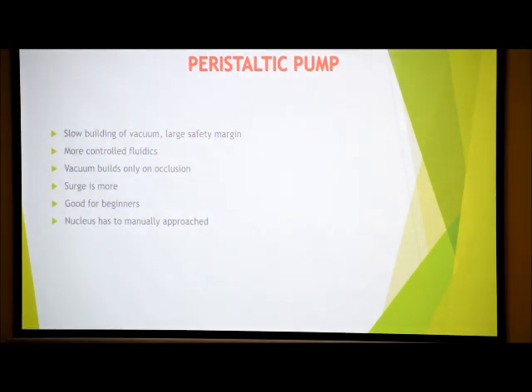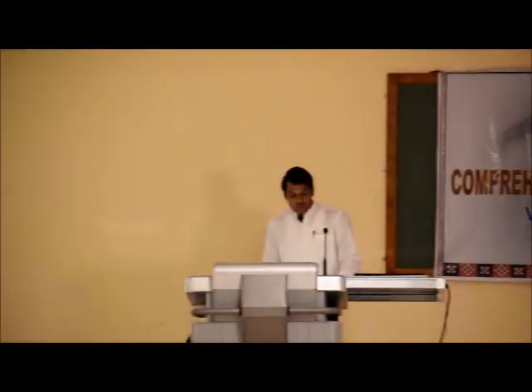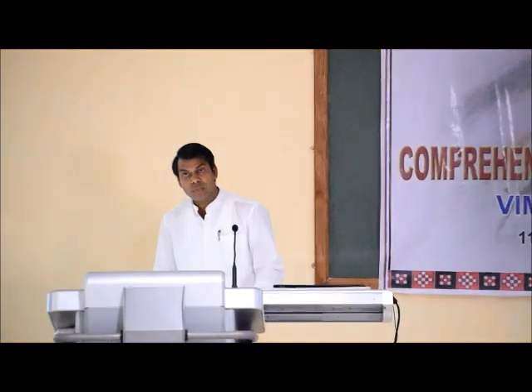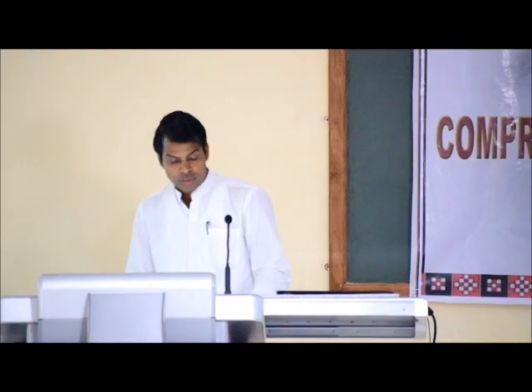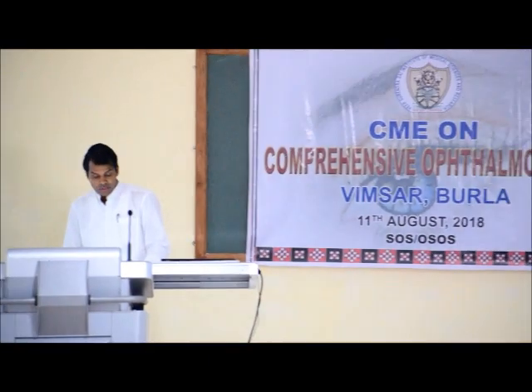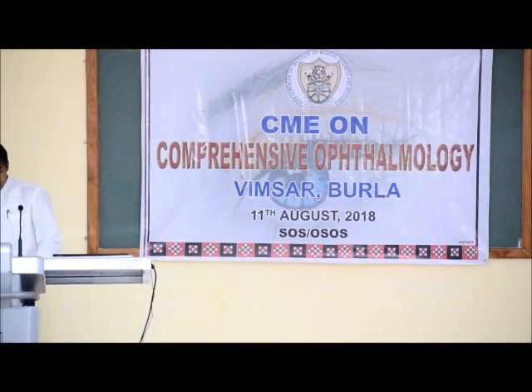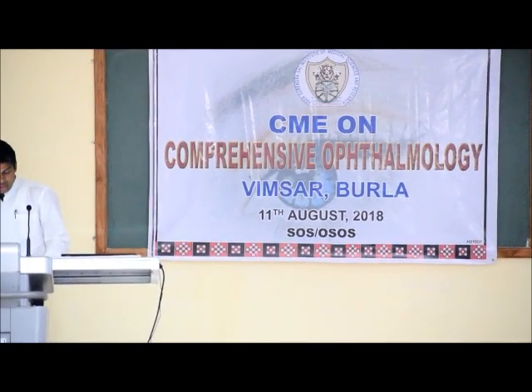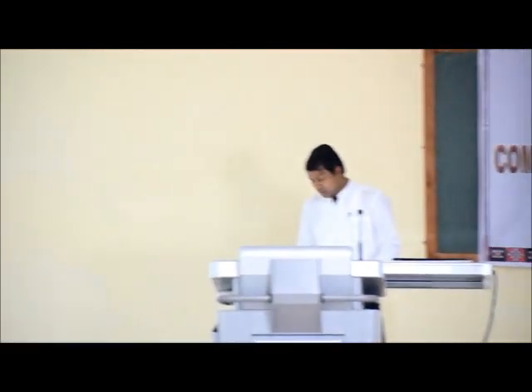Peristaltic pumps are safe; the vacuum build-up is slow and safe, with more control over fluidics. Vacuum builds up only on occlusion. Surge is more good for beginners. I have come to surge. What is surge? The nucleus has to be manually approached with the phaco tip.